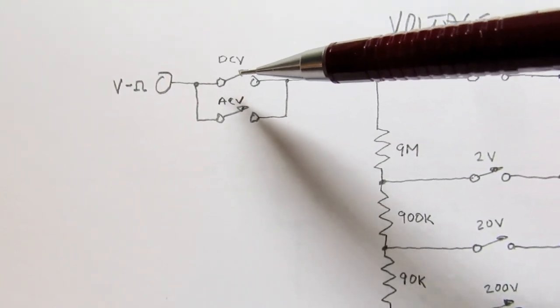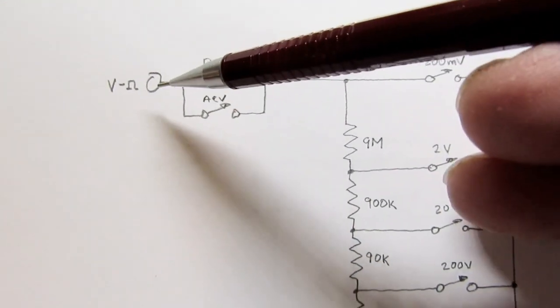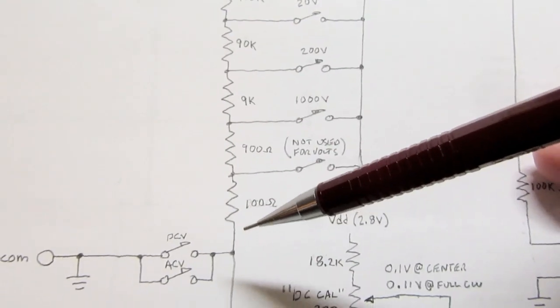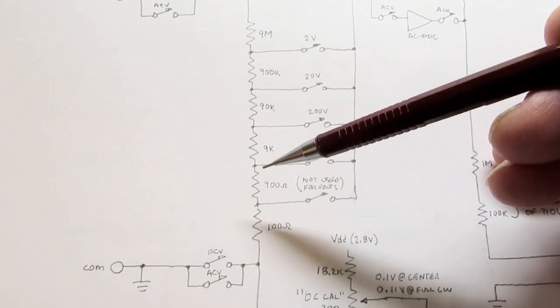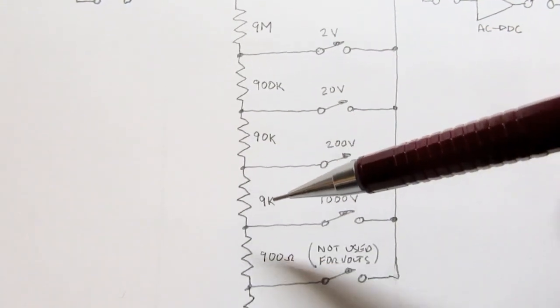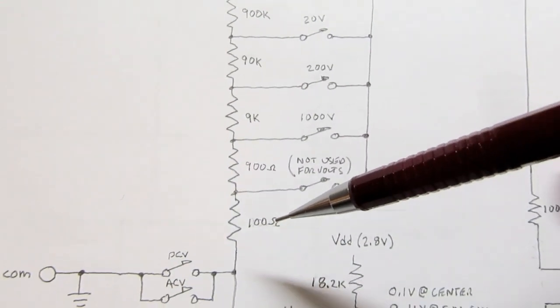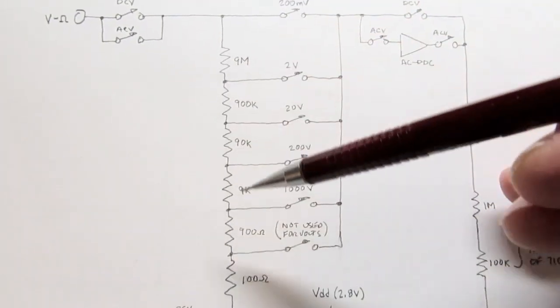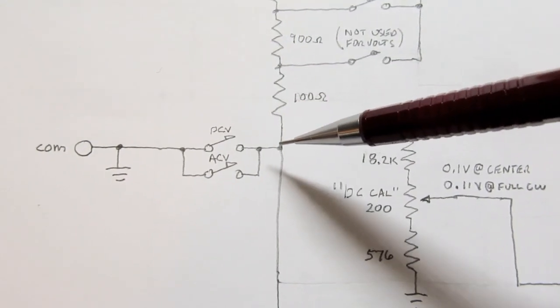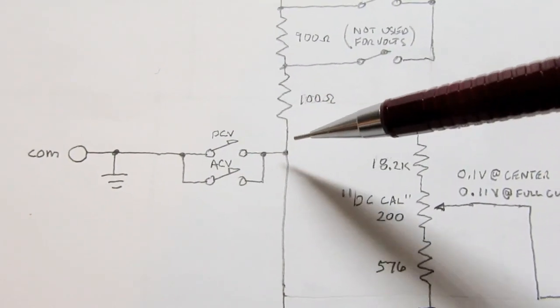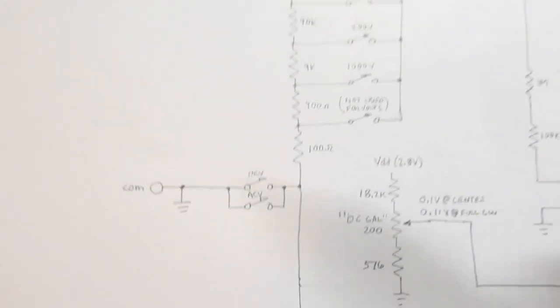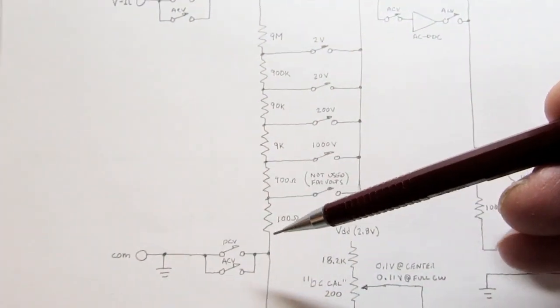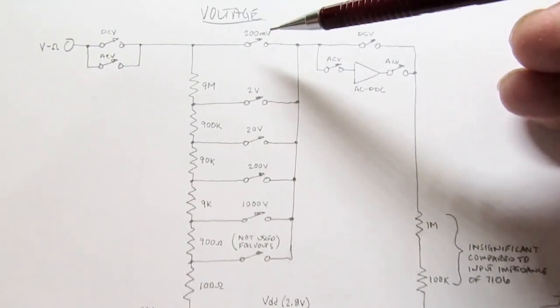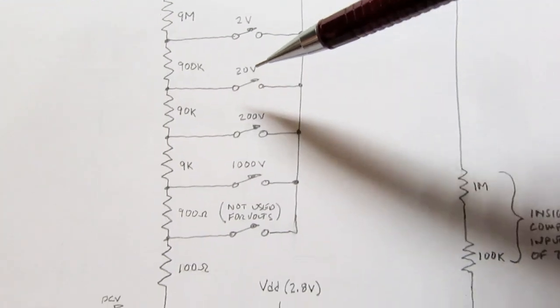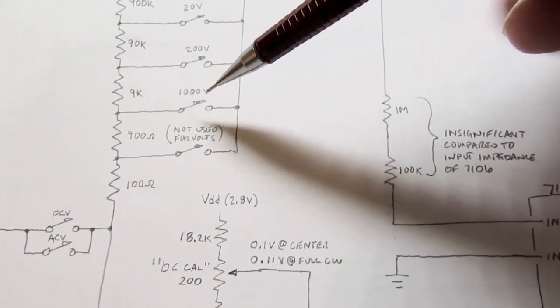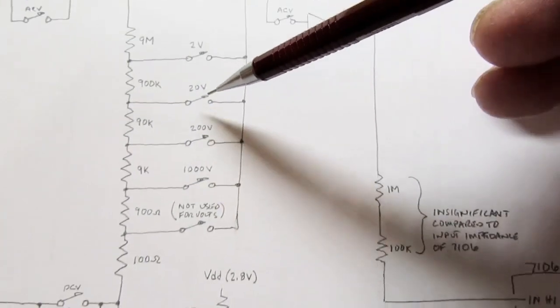If the meter is currently in one of the DC volts modes or one of the AC volts modes, then this jack is connected to the top of this big voltage divider made out of 6 precision resistors. A 9 meg, a 900K, 90K, 9K, 900 ohms, and 100 ohms. If you add all those up, it becomes 10 megs for this entire assembly. And then the bottom of it, once again, if you're in any of the DC volts or AC volts modes, the bottom of that divider is connected back to common. So you impress whatever voltage you're measuring across this big divider. Then, depending on which range you're in, 200 millivolts, 2 volts, 20 volts, 200 volts, or 1000 volts, or 750 if it's AC, one of these switches will close.